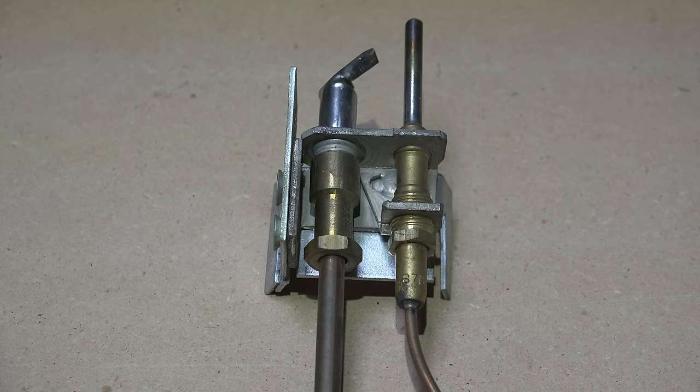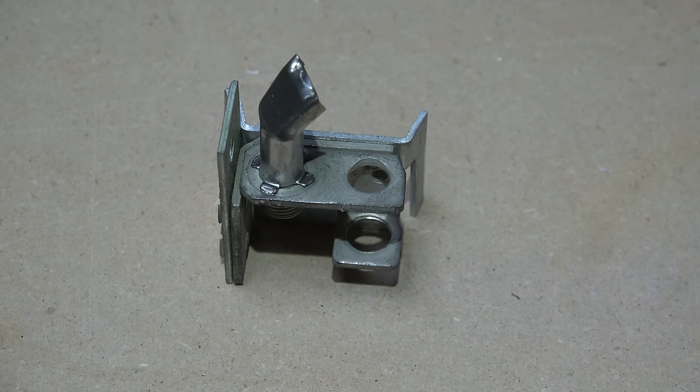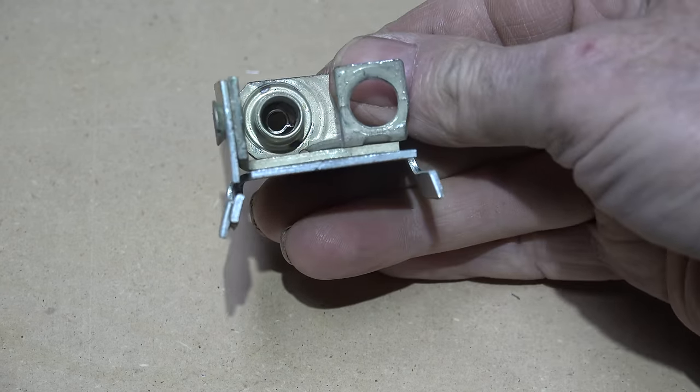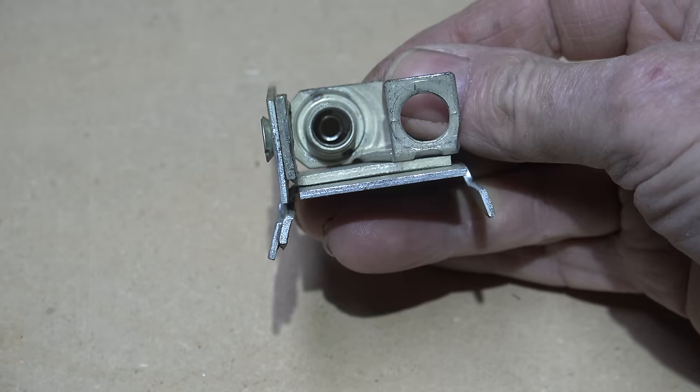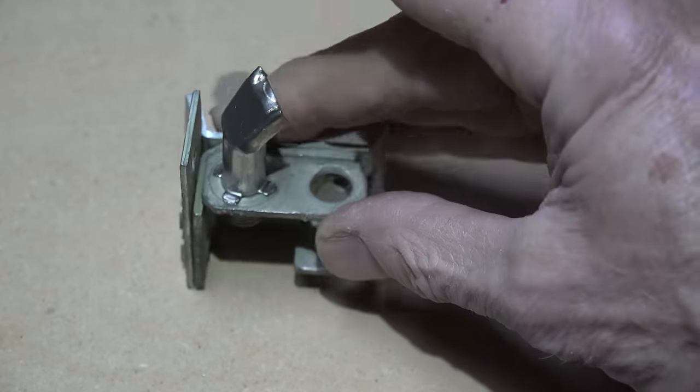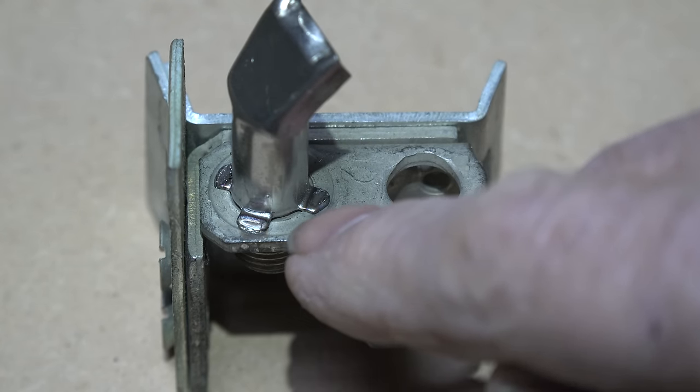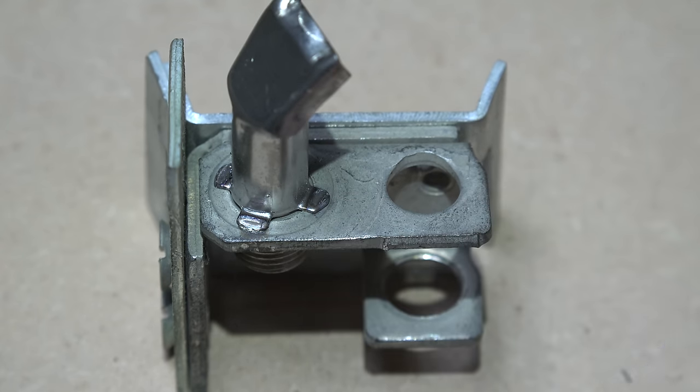Now here's the pilot disassembled. The gas goes right up through that hole there and comes out up here, where these tabs are. There's just a little bit of space there that actually draws in primary air, so because there's a negative pressure in there, that's why we end up with a blue flame coming out of here.